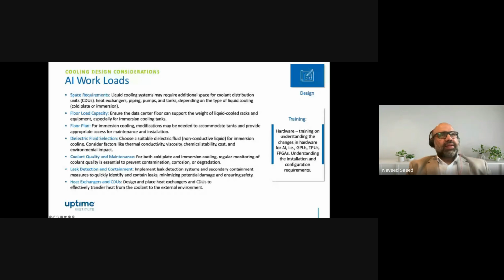There are some other design considerations that need to be considered by data center professionals. If you are on the design side or operation side, managing the capacity of your data center, you need to be mindful of these requirements, and some of these are listed on this slide. Space requirement is one of them. A liquid cooling system may require additional space for cooling distribution units (CDUs), heat exchangers, piping, pumps, and tanks, depending upon the type of liquid cooling, cold plate or immersion. Again, it depends upon how you want to split your white space and the gray space or the cooling gallery. Where do you want to put your CDUs and heat exchangers?